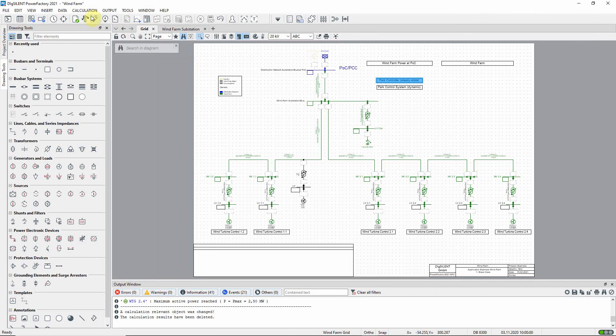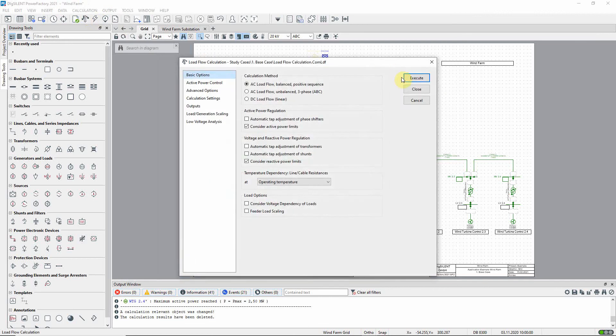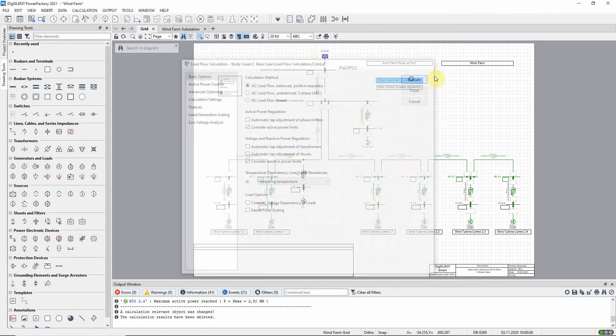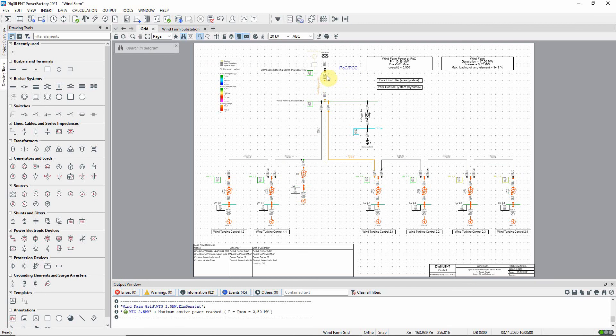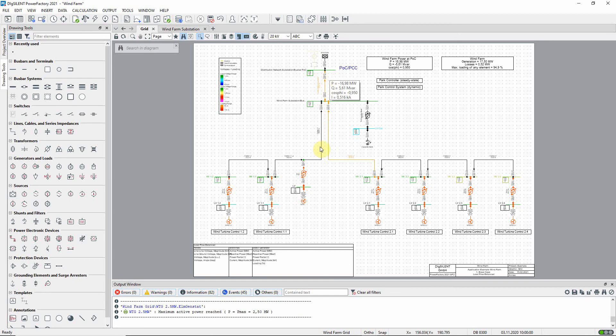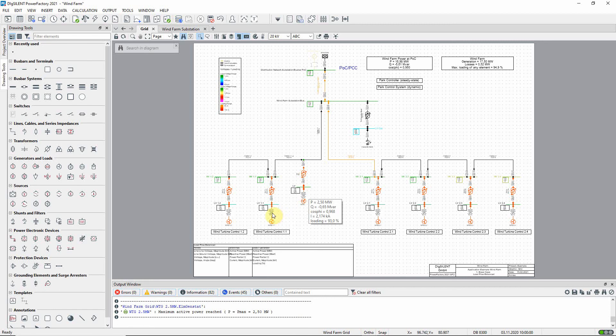Run another load flow. You can see that at the point of common coupling around 17 megawatts of active power is being fed into the grid. Cos phi is controlled to 0.95 according to the characteristics that we set in the wind farm controller. Notice that the new generator is now absorbing the same reactive power as the other generators.